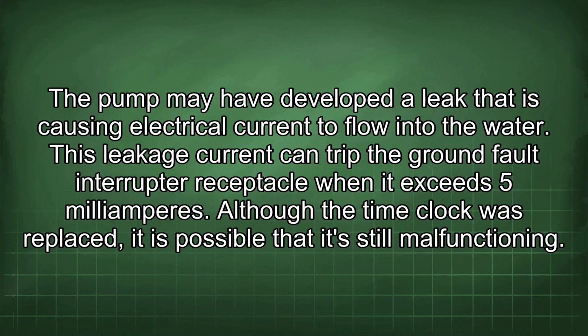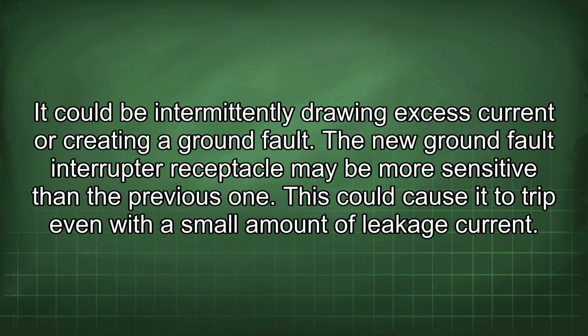The pump may have developed a leak that is causing electrical current to flow into the water. This leakage current can trip the ground fault interrupter receptacle when it exceeds 5 mA. Although the time clock was replaced, it is possible that it's still malfunctioning. It could be intermittently drawing excess current or creating a ground fault. The new ground fault interrupter receptacle may be more sensitive than the previous one. This could cause it to trip even with a small amount of leakage current.